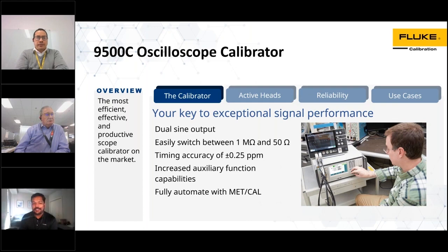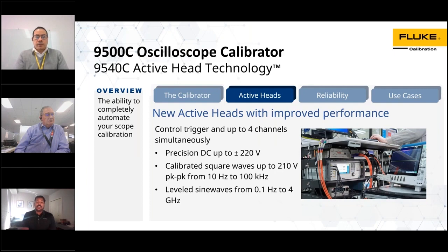Let's talk a little bit about the active heads. The new active heads have improved performance. You can control the trigger and up to 4 channels simultaneously. This allows precision DC voltage measurement up to 220 volts. You can calibrate square waves up to 210 volts peak to peak from 10 hertz all the way up to 100 kilohertz. You can calibrate leveled sine waves from 0.1 hertz all the way up to the 4 gigahertz limit.